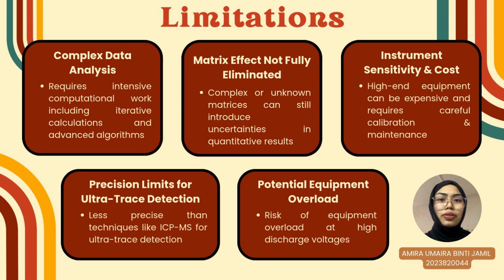Next, we have instrument sensitivity and cost. The high-end equipment required for FSLIBS can be expensive and demands careful calibration and regular maintenance, which adds to operational complexity. Another limitation is its precision in ultra-trace detection. Compared to more sensitive techniques like ICP-MS, FSLIBS may not perform as well when detecting elements at extremely low concentrations. Lastly, there's the risk of equipment overload, especially when operating at high discharge voltage. This could lead to system failure or damage if not properly managed. Despite these limitations, many of them can be addressed with proper setup, software support, and experience in handling.